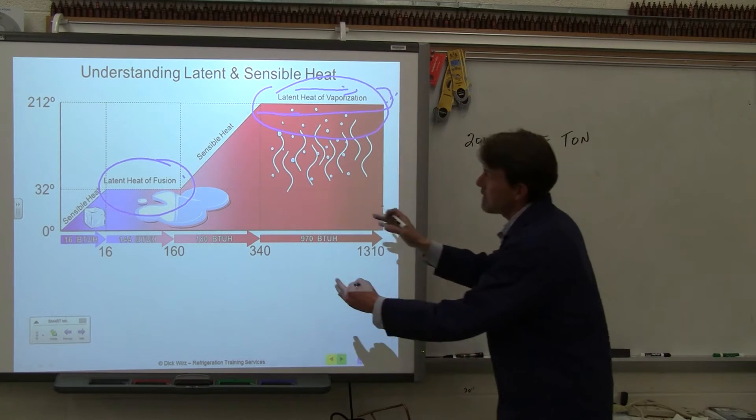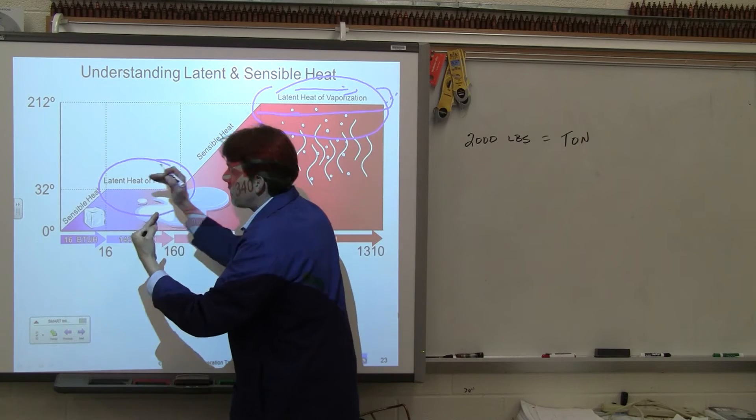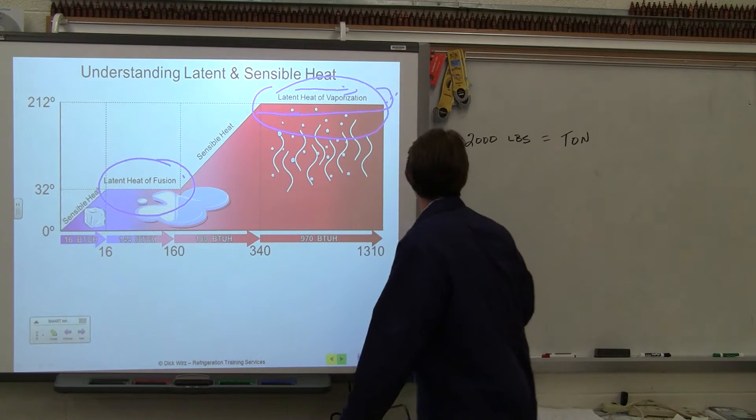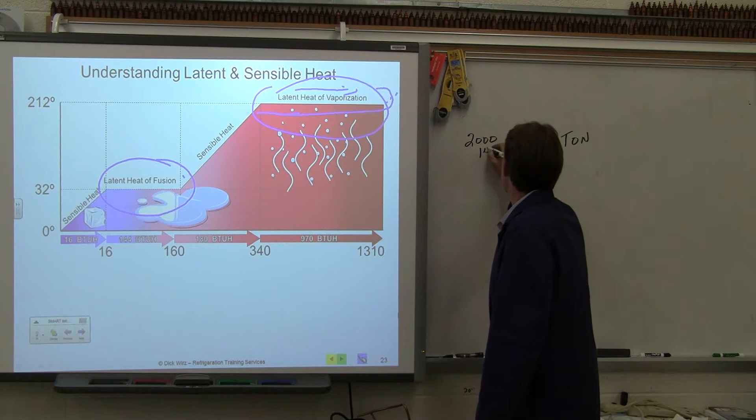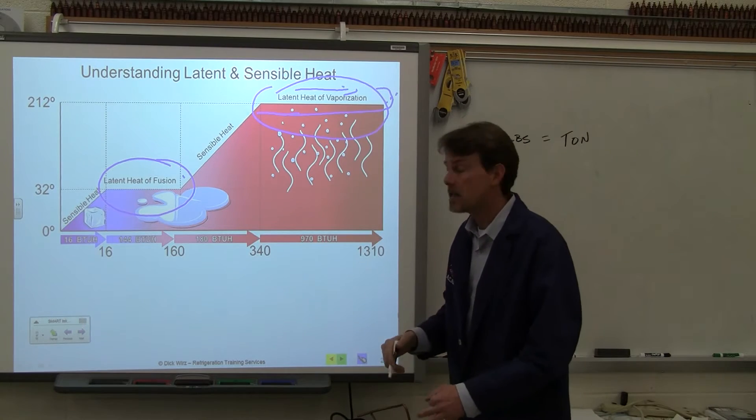If we wanted to calculate how many BTUs is needed to melt, or if I went the other way and took away the heat, then I could make a 2,000 pound block of ice by multiplying this by 144 BTUs, and that gives me the number 288,000 BTUs.